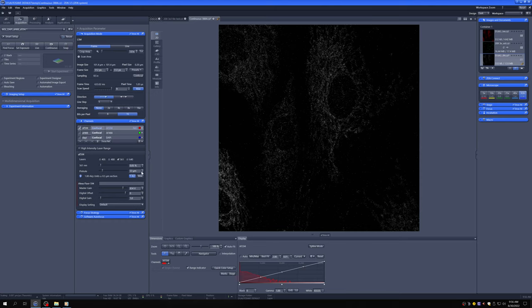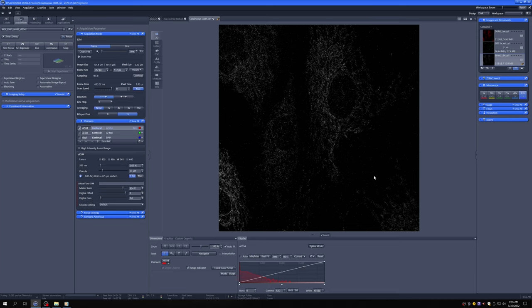The other reason is that you may reach this point where if you increase the laser further, you don't actually see any changes in intensity because all your fluorophores are being excited and there's nothing left for the laser to excite. So if you're in that situation, averaging is really the only way to increase the quality further. An additional thing that's a disadvantage of averaging is that you can't average different amounts for different channels. So if you have one channel that looks like this but the others are very good, you may want to average a lot in that channel and not in the others, but that's not possible.